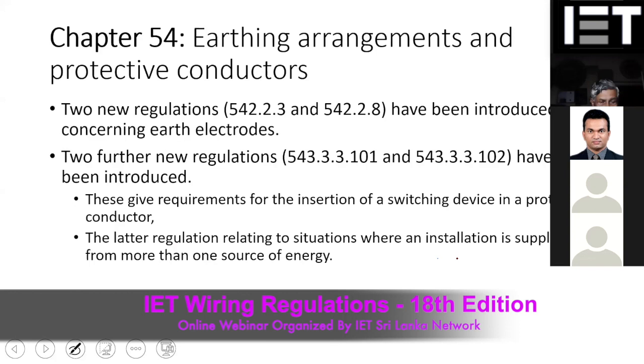But when you are going with the foundation earthing, you have to consider the corrosion and other things, so those new regulations are added for corrosion prevention. And also, if you have multiple sources in a building, how do you do the earthing arrangement? Most of the time people ask: if you have multiple sources, two generators in two locations feeding into one installation, and two transformers feeding into one location, what should be done for the earthing arrangement, whether we connect them together or isolate them?